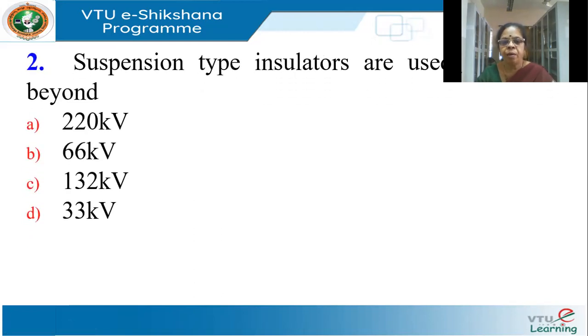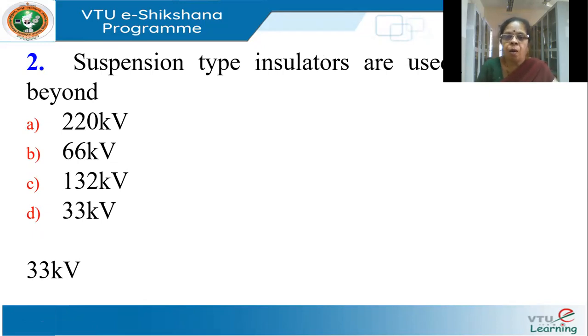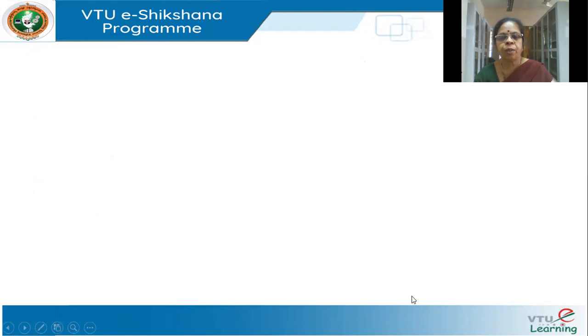Suspension type insulators are used for voltages beyond how much? They are used for voltages higher than 33 KV. Below that you can use pin insulators. Pin insulators become uneconomical for voltages above 33 KV, so we go for suspension type insulators. The correct answer is 33 KV — beyond 33 KV we use suspension type insulators.